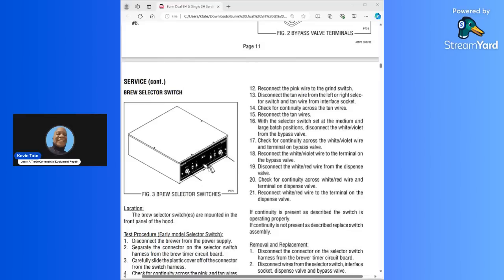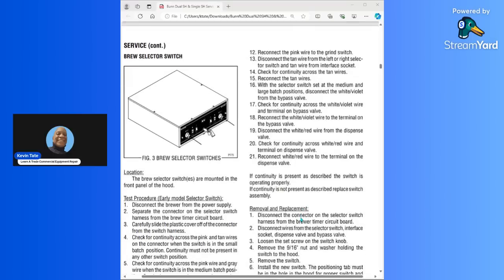Disconnect the tan wire from the left or right selector switch and tan wire from interface socket. Check for continuity across the tan wires. Reconnect the tan wires. With the selector switch set at the medium and large batch positions, disconnect the white violet from the bypass valve. Check for continuity across the white violet wire and terminal on bypass valve. Reconnect the white violet wire to the terminal on the bypass valve.